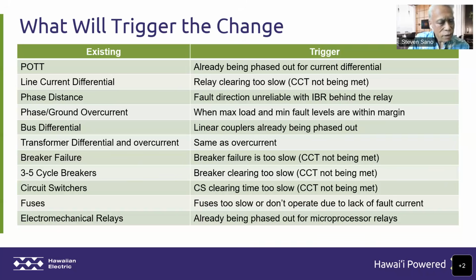Not being fast enough. Circuit switchers, same thing, critical clearing times. Fuses, when they get too slow or don't operate for a lack of fault current, miscoordination. We're also changing fuses out for reliability, so there are other opportunities and triggers for fuses. But again, it's primarily the decrease in fault current levels that are causing that. Electromechanical relays, again, it's an ongoing process with that. If anything, we just have to keep going and maybe go faster on that.